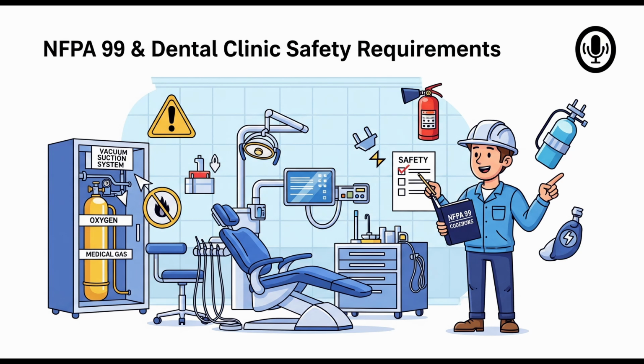It is. The code does mention slightly relaxed rules for very small quantities of gas, like 300 cubic feet total or less. But even then, the basic handling precautions in Section 11.6.2 still apply. And what are those key handling precautions? Things like always using the correct fittings, oxygen fittings only for oxygen, never trying to force or adapt fittings between different gases, and a really important one, Section 11.5.2.2.3 prohibits transferring gas from one cylinder to another, transfilling, within the patient care vicinity. That's something only suppliers should do in controlled environments.